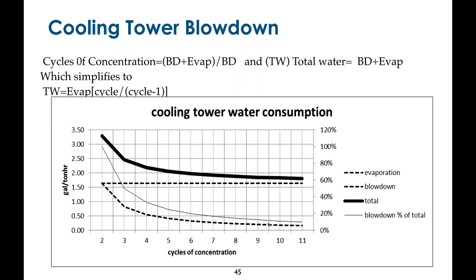We often think of five cycles of concentration as a reasonable number. What that means is if you've got, say, 50 parts per million of silica in the incoming water, and you're trying to control your cycles of concentration or silica level in the chiller tubes in the recirculating flow to say 150 parts per million, well, the cycles of concentration you need to achieve that is 150 divided by 50, or 3.